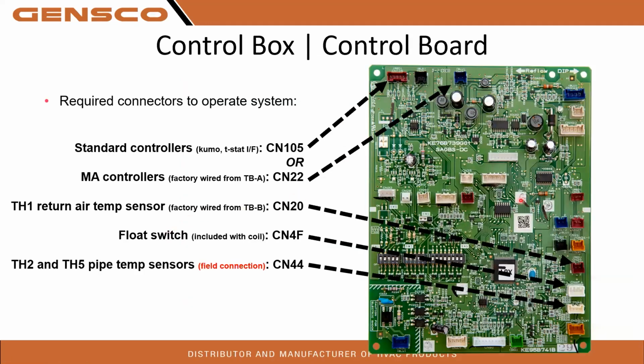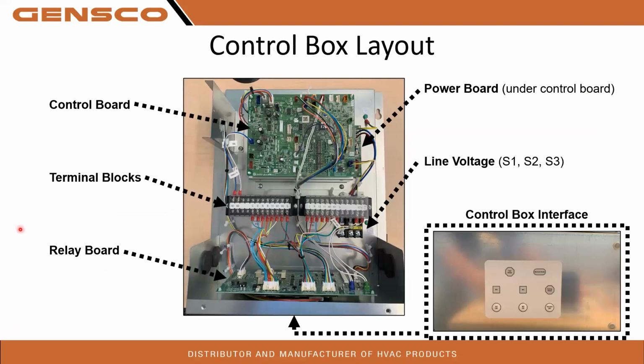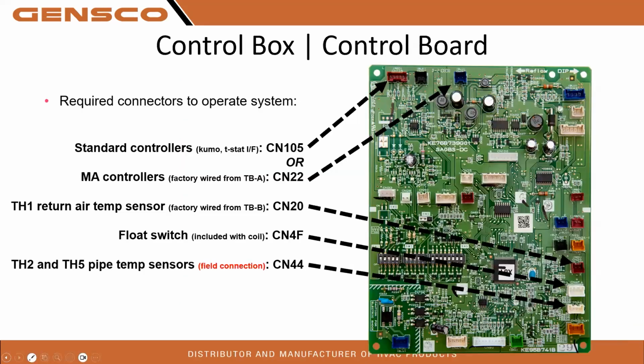And here is an exploded view of the control board. So again, this is your CN105 connector that you're going to hook your MHK2 thermostats up to, your Kumo cloud, or your PAC 445 interface. A lot of the connectors on here are pre-set up from the factory. This one here is for your MA controller, which actually, if you come back on this slide here, if you're using a wired Mitsubishi thermostat, it is going to connect right here on the M1, M2. And it's factory wired into the MA control spot right there that I was just highlighting on the other slide, which is right here. So again, factory wired, shouldn't have to mess too much with that.